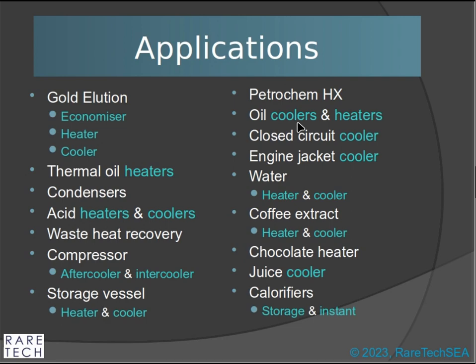But oil coolers are notorious for running laminar because the pressure drops end up so high. So then how on earth do you get the heat to get into it? Typically, for oil coolers and heaters, we put that oil on the shell side and then create mechanical turbulation to actually get the mix in that you require.